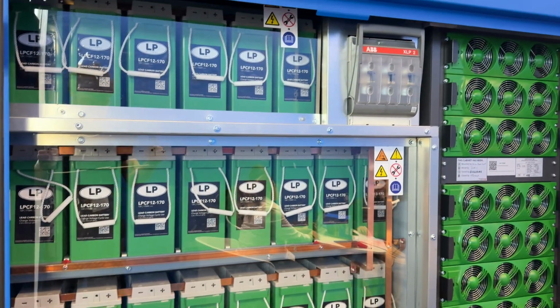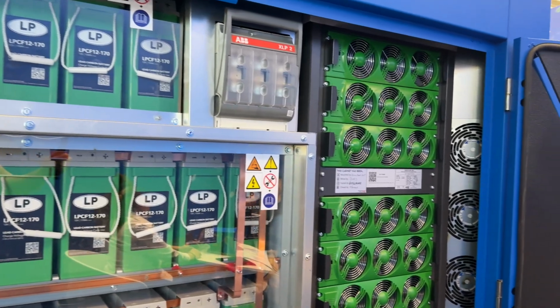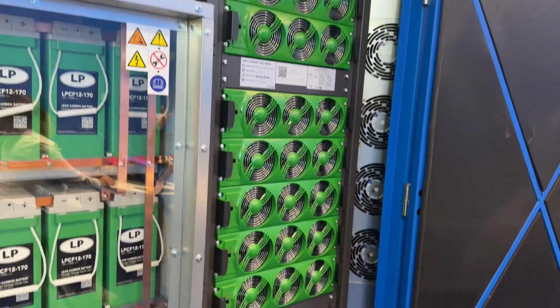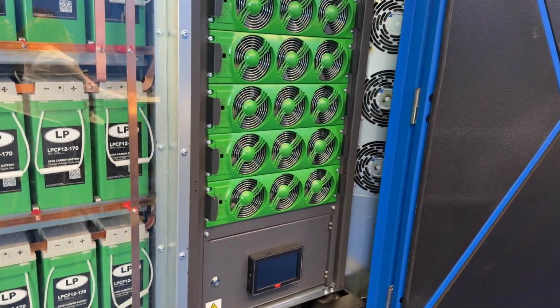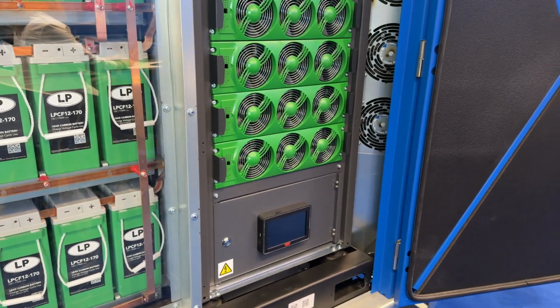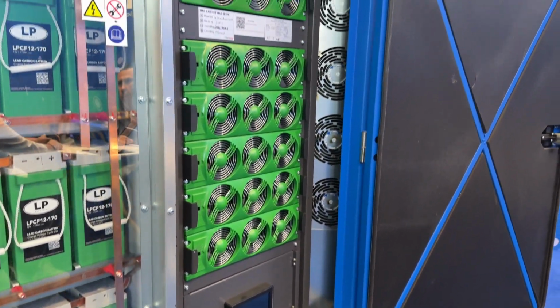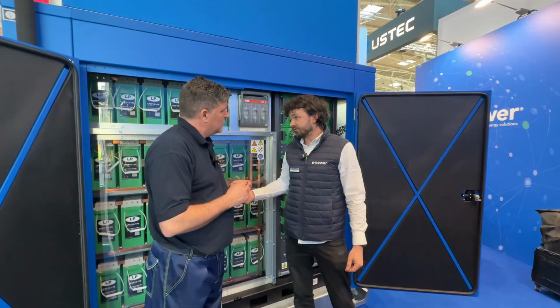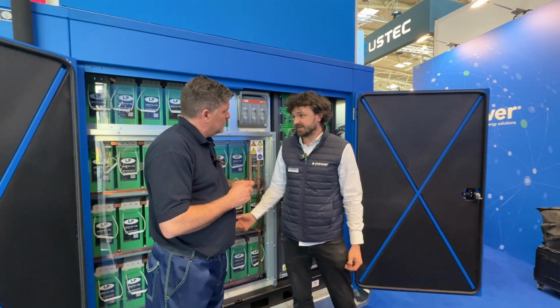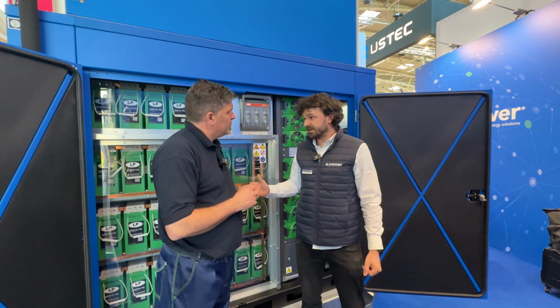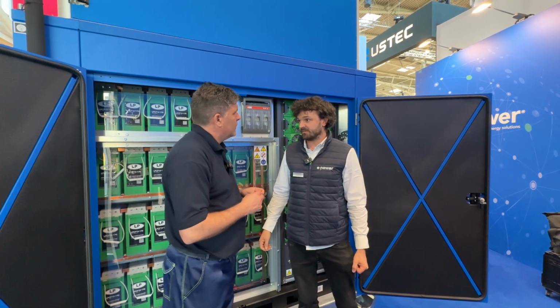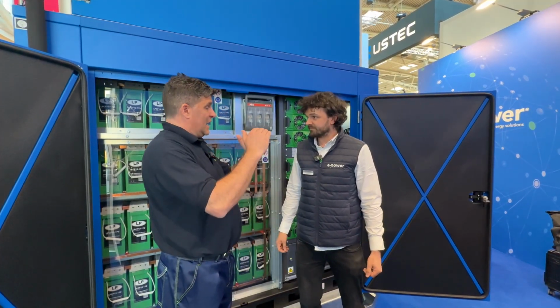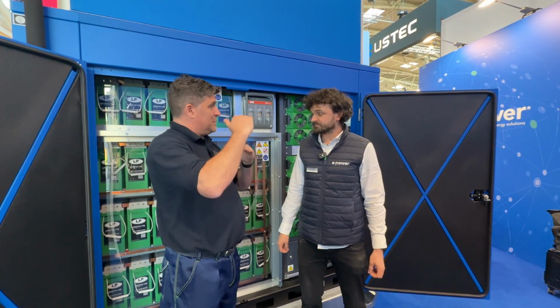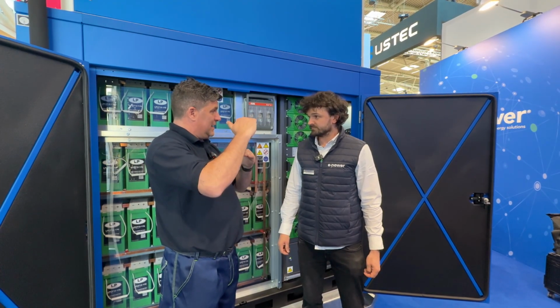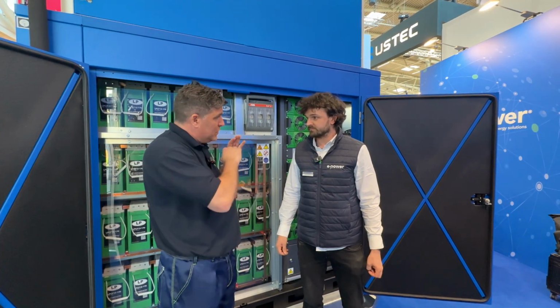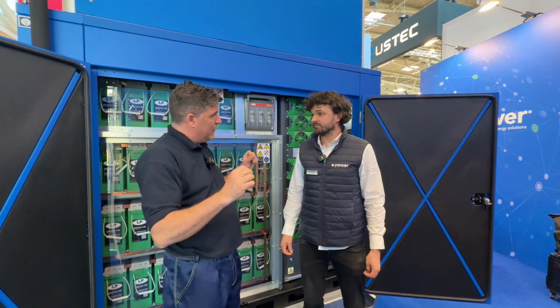The P-Grid solution is designed to save people money. It's a hybrid unit combining batteries with a generator, optionally also a mains connection. With the batteries, we can deliver peaks that normally would be covered by a 200 to 250 kVA generator, and we feed it with just a 40 kVA generator. That saves people a lot of money, because they're having to pay their power grid for that peak amount. When you shave that off, the costs are cut down.